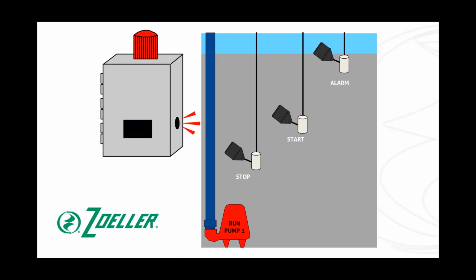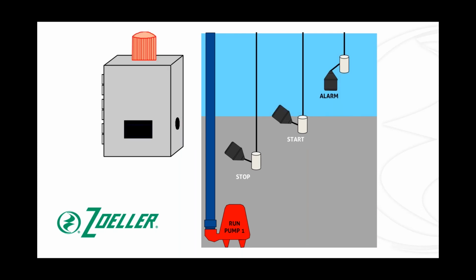So now the water level has risen high enough to activate the high level alarm switch this time. You will now have your audible and visible alarm features activated on your control panel if it is so equipped. This will alert the user of a potential problem. But since we have a trusty Zoeller pump in here and the flow of water coming in has slowed up a little bit, our trusty Zoeller pump is able to catch up and discharge the water.